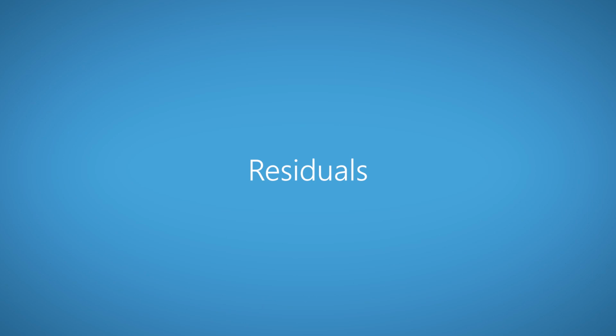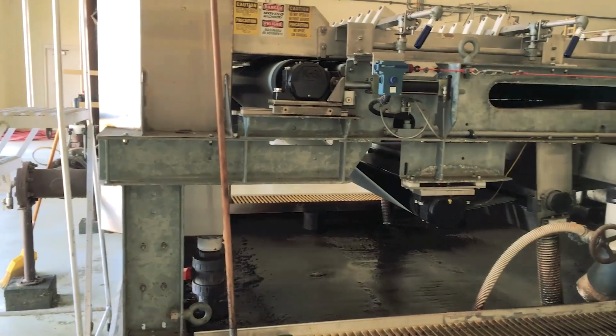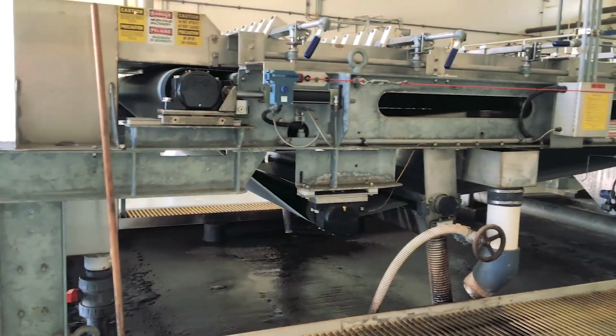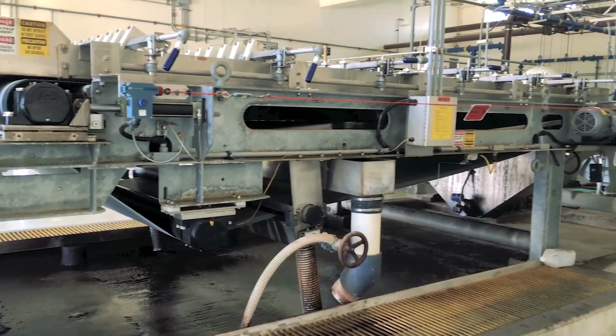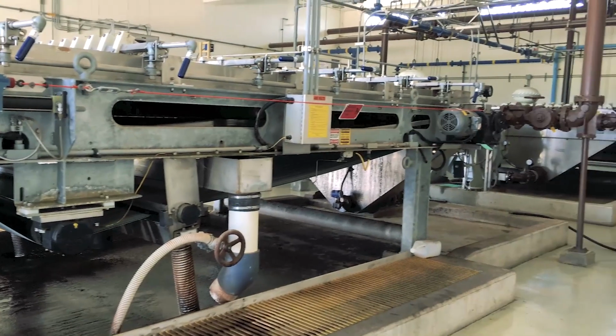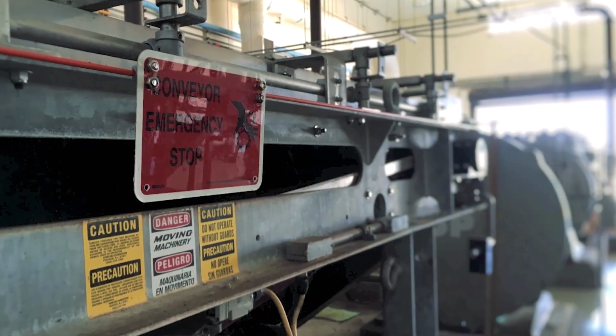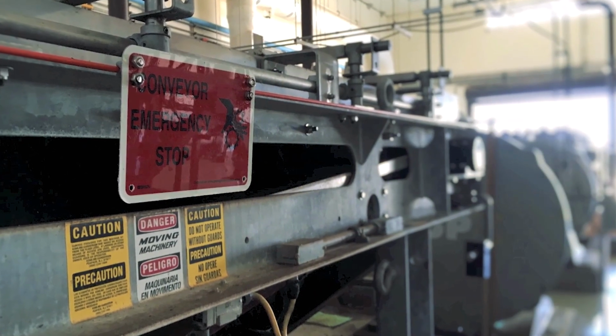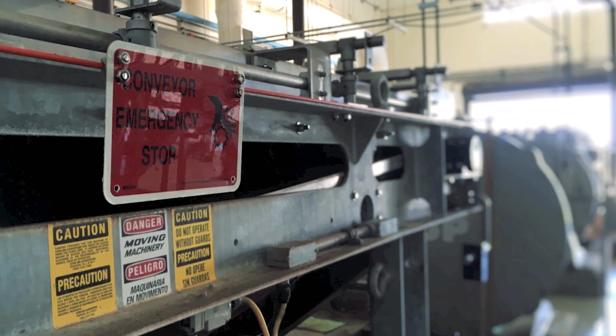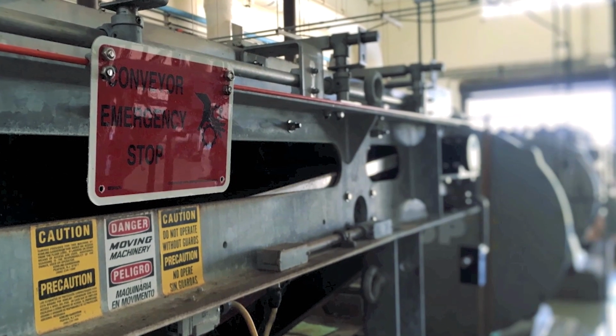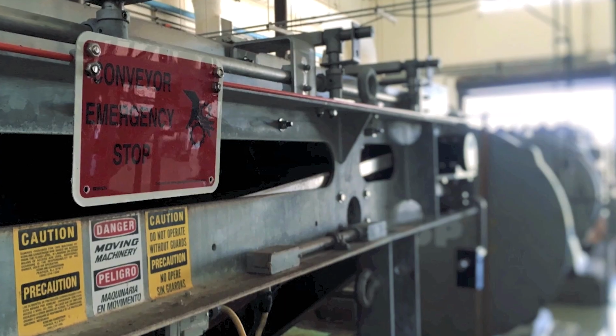2 gravity belt thickeners are housed in the residuals building. The GBTs are used to thicken the waste-activated sludge generated by the secondary clarifiers. Each GBT unit also contains a trip cord connected to an emergency stop switch to immediately stop the belt drive and shut down the entire system in the event of a problem.